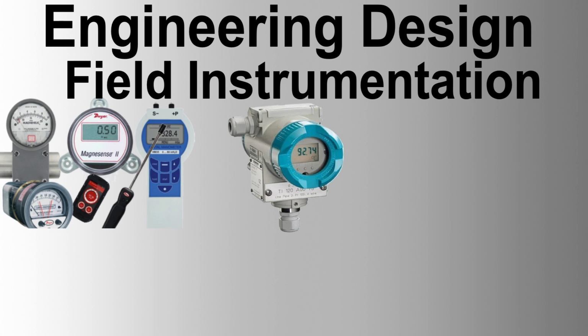Transmitters must be provided with local digital indication, and the accuracy must be better than 0.075%. Pressure gauges, differential pressure gauges.